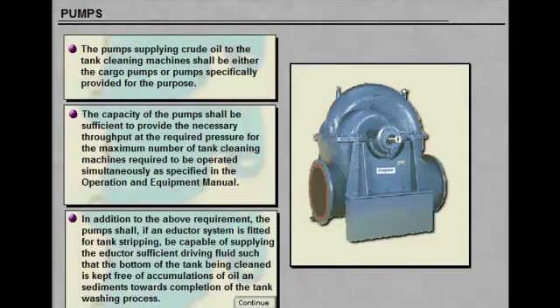In addition to the above requirement, the pumps shall, if an eductor system is fitted for tank stripping, be capable of supplying the eductor sufficient driving fluid so that the bottom of the tank being cleaned is kept free of accumulations of oil and sediments towards completion of the tank washing process.